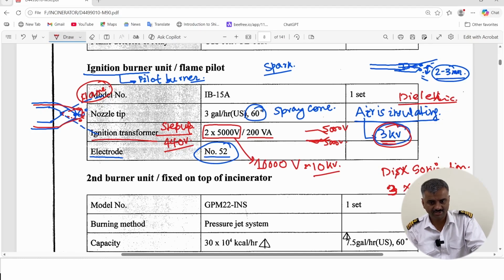So at least 9000 volts are required to create the ionization, to create the spark, and then establish a stable pilot flame over here. To be on the safe side, 9000 volts are required and what we supply is 10,000. The same concept applies to the boiler pilot burner also. That is why we require 10,000 to 11,000 volts for the boiler pilot burner electrode sparking. Okay, we understand that, right?